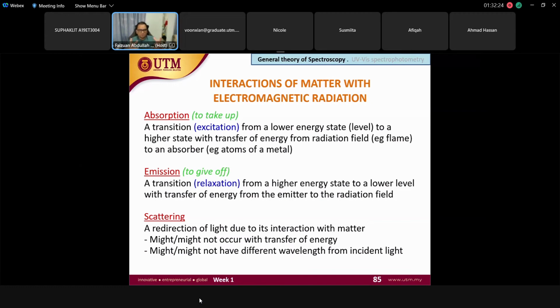That can only be measured after the calculation by the detector and the instrument itself. After the calculation, this is the concentration of aurum inside the sample, because this amount of energy has been absorbed, and then it is calculated back against the volume of the sample, and the computer will translate it into information.